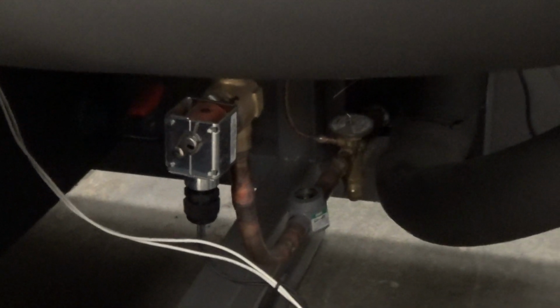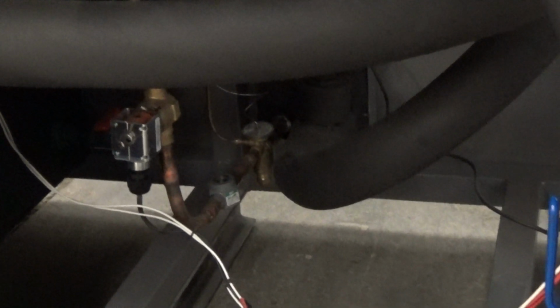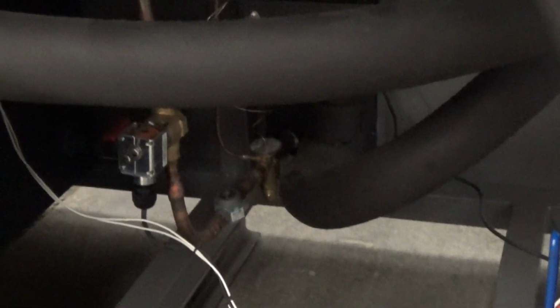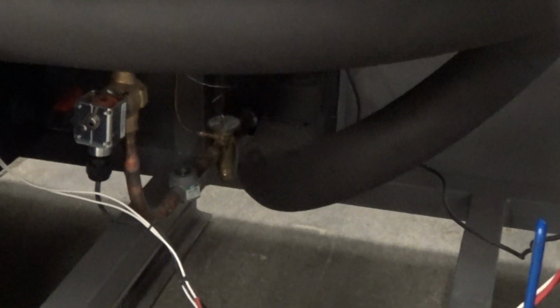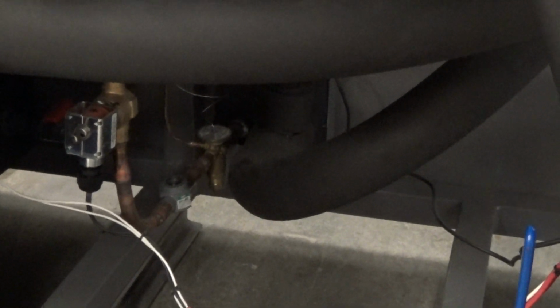We do have refrigerant sight glasses on all our E-Chills, which is nice. And we also have a solenoid valve here, a positive shutoff solenoid valve for the refrigerant. That's a nice feature too. The chiller does operate on pump down, so after each compressor cooling cycle, that solenoid valve will close there, and the compressor will pump down, which prevents liquid refrigerant from coming back into the compressor. Ask any HVAC guy, in particular with smaller chillers. That's a really nice feature.